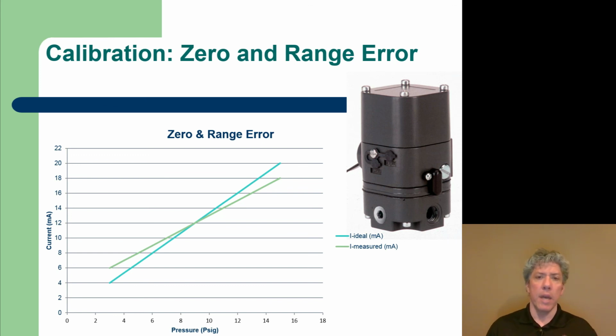you typically use a current signal, and the standard for current signals is 4 to 20 milliamps. And so it's important that 4 milliamps correspond to about 3 psi and 20 milliamps correspond to 15 psi, or that the ranges of the current correspond to the range of pressure and therefore the range of motion of the valve. So what this device does is it brings in the current signal, takes in air pressure from whatever air source you have in the plant, and produces a pressure signal proportional to the current signal.